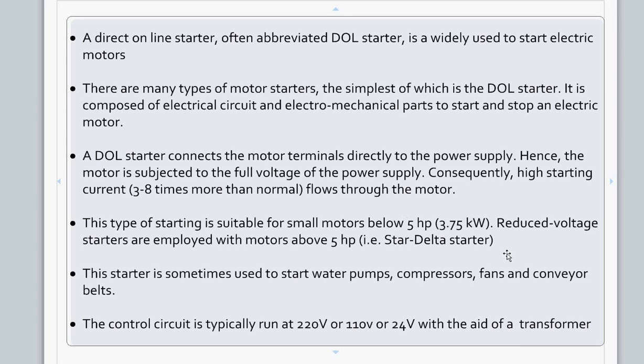This type of starter is only suitable for small motors, basically below 5 HP. For motors above 5 HP, it is better to use the star delta starter or some electronic starters. This starter is sometimes used to start water pumps, compressors, fans and conveyor belts. And the control circuit depends on the coil. It can run on 220 volt or 110 volt or 24 volt. In this case, you need to add the transformer to step down the higher voltage.